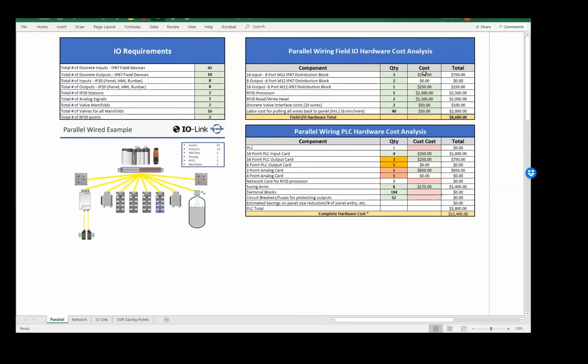Definitely. Then our calculator does a quick calculation for all the individual terminal block terminations. We figure right around $194, plus or minus 10%. Yep. We'll just say a dollar per terminal block to be safe. Yeah. And then because of our output devices, we have 52 devices. We'll say $20 a point, either for a fuse and fuse block or circuit breaker. Oh, perfect. And then again, soft savings, we can talk about this later, estimated savings on panel size reduction. There's definitely benefits there, but just from a hardware perspective, we look at this system, just from hardware, is going to take you $13,634. Yep, with labor, right?